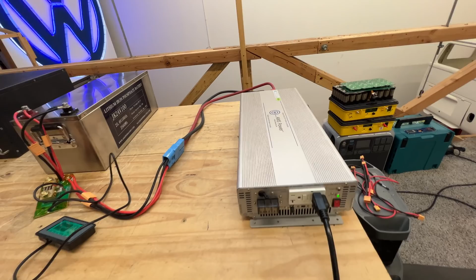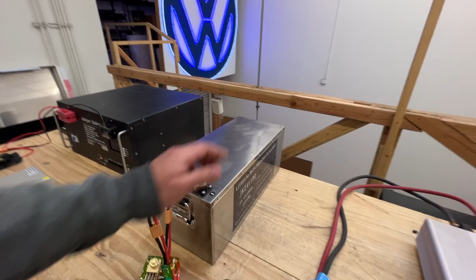That's just connected to the thing here, so we're going to quickly see if we can load it with 100 amps - this is the max it will do - and then check capacity. Okay, here we go, 90 amps. Let's adjust it to get 100 amps... 94, 95... all right, 100 amps, 2.4 kilowatts. Let's see how the battery does here.